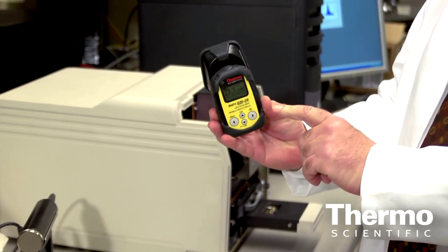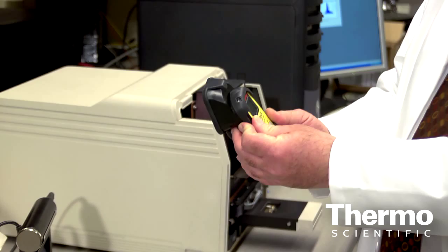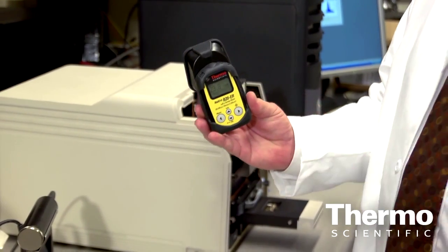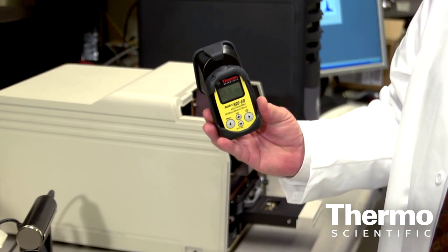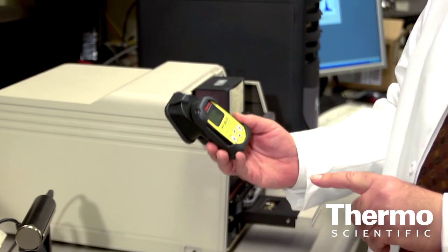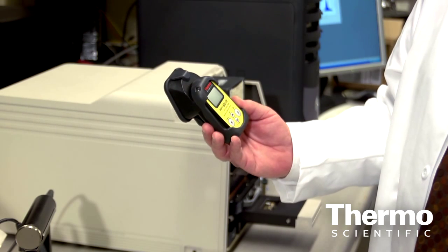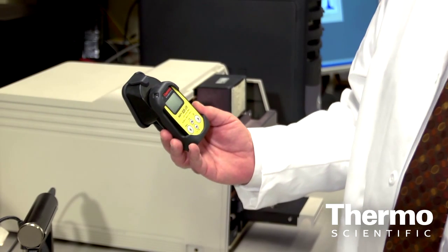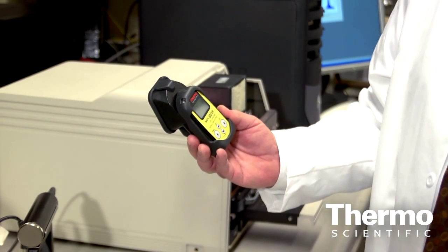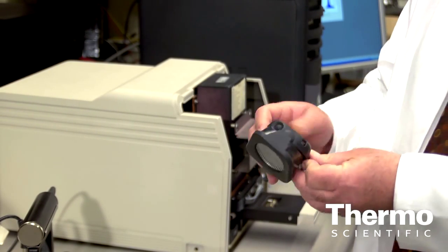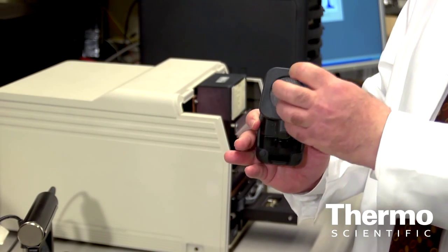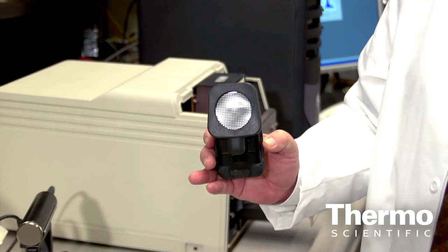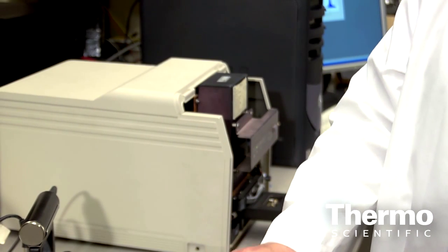Then we have this device. This is also RADiG, but it has something else on the back. It has this thing here, right here. This device is based on gas. However, it is capable to measure different types of radiation. It can measure highly penetrating radiation like gamma rays, but it can also measure very non-penetrating radiation like alpha. It has a thin window in the back. It can actually pick up alpha particles from surfaces or from contaminated areas.